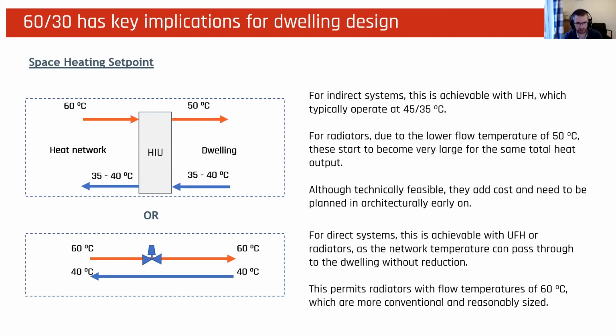architectural process. The alternative is to go for a direct system, which is a real challenge on tall systems because the pressures become untenable to enter people's dwellings. But it is an option where you remove the plate heat exchanger from the HIU and just have it for the hot water, and the space heating goes direct through to the heat network, which means we don't need that step down in temperature, and we can pass that 60 degrees straight through and get 60-degree flow temperature to the rads, and they start to become a little bit smaller than the 50.